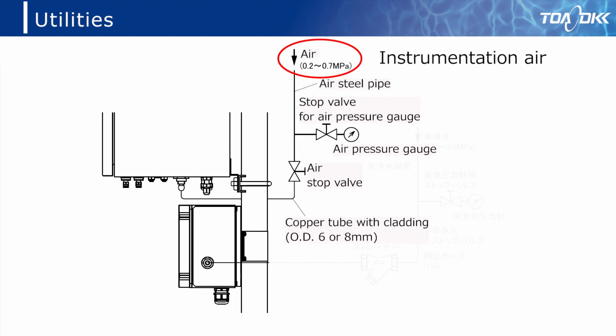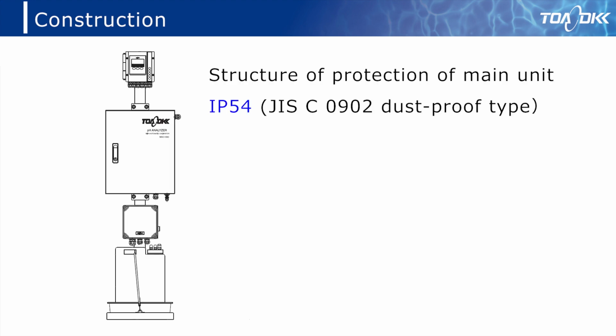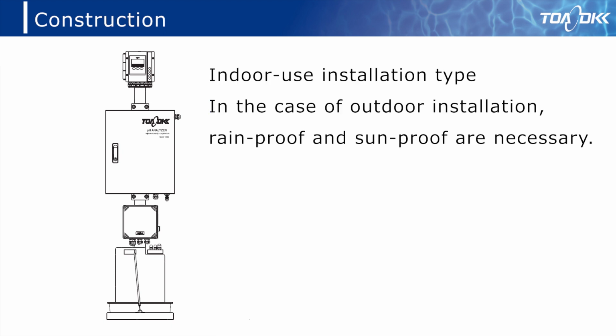Supply of instrumentation air is required. This is used to raise the holder and inject the chemical. Prepare a pressure of 0.2 to 0.7 megapascals. This section explains how the main unit is protected. Its structure is IP54 and dustproof type. Basically, please install the main unit indoors. In the case of outdoor installation, rainproof and sunproof protection are necessary.